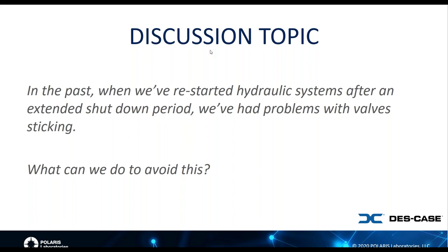And depending on the amount of oxidation that is present there, you may have some of those situations that Mark just talked about. So what I would recommend is for the hydraulic system to be restarted, let the oil go through all the galleys, all the nooks and crannies, and re-lubricate the whole system, making sure that there are no weird noises. If you start hearing weird noises, then maybe better to shut it down and go ahead and do a total oil change. But if everything sounds great, it's best to send in a sample just to find out the level of oxidation that you have there.